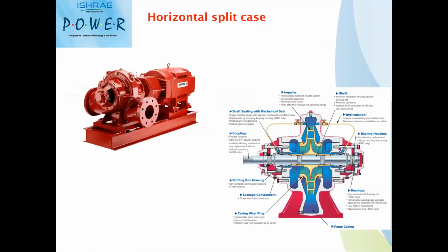When it comes to horizontal split case, you can see this is a heavy duty pump wherein the pump is designed with a split casing. This is a split casing. Some manufacturers will have an angled split, or some manufacturers will have a horizontal split where the casing is split. So whenever you want to access the internal parts, you can open these bolts and take out the upper casing to access the parts of the pump. That's why it is called a split casing pump. This is a heavy construction pump where the motor and pump shafts are connected again through a long coupled design, and it is mounted on a common base plate.